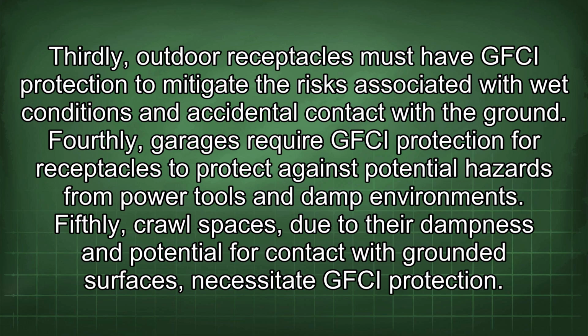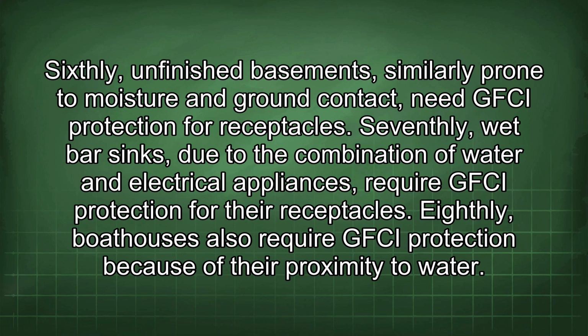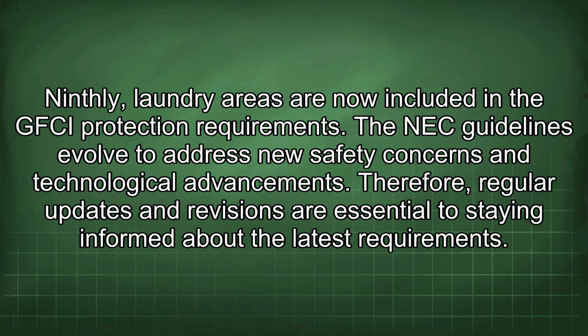Fourthly, garages require GFCI protection for receptacles to protect against potential hazards from power tools and damp environments. Fifthly, crawl spaces, due to their dampness and potential for contact with grounded surfaces, necessitate GFCI protection. Sixthly, unfinished basements, similarly prone to moisture and ground contact, need GFCI protection for receptacles. Seventhly, wet bar sinks, due to the combination of water and electrical appliances, require GFCI protection for their receptacles. Eighthly, boathouses also require GFCI protection because of their proximity to water. Ninthly, laundry areas are now included in the GFCI protection requirements.